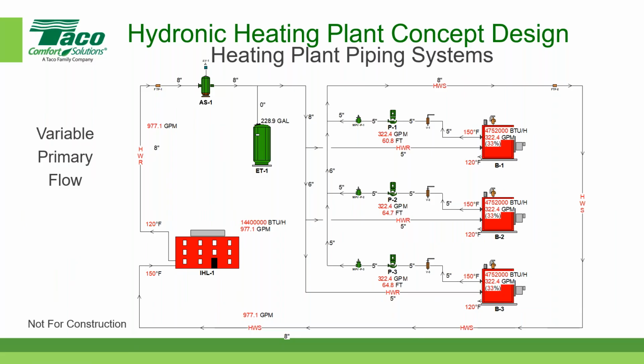Okay, so what if the boiler turndown ratio was, I'll use two extremes. Let's say the turndown ratio for the boiler could be down as low as, say, 40%. If your load drops below 40%, then that implies that you'd have to have a bypass to maintain the minimum flow required by the boiler. But if the boiler, let's say, did not have that lower turndown ratio, maybe it only had from 100% down to 60%, then that would have a much different implication of how you configure your pumps and your boilers.